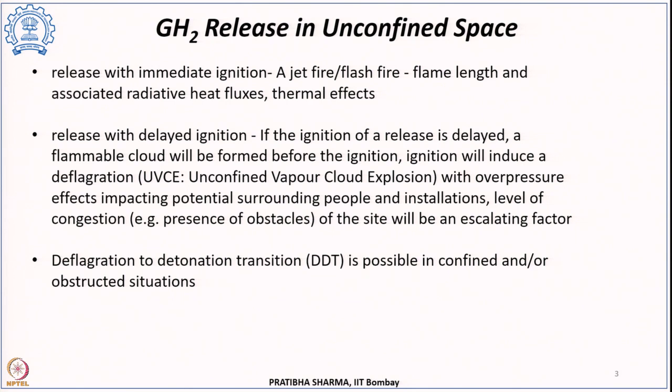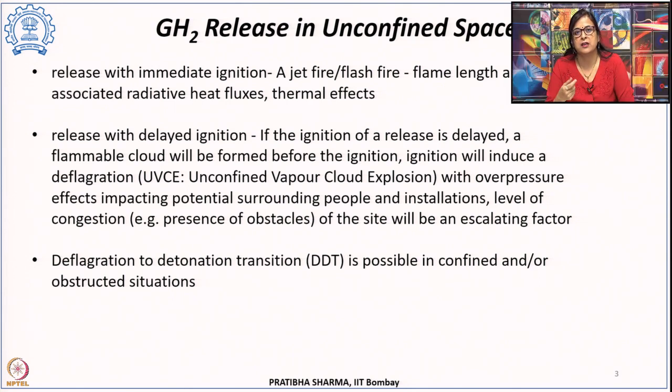By jet fire we mean that the hydrogen which is being released didn't get sufficient time to mix with the oxidizer. As it comes in contact with the ignition source, burning takes place, and since the outer surface has mixed with the oxidizer, that burns. However, the inner region is still concentrated with fuel and does not have sufficient oxidizer. So that appears as a jet fire.